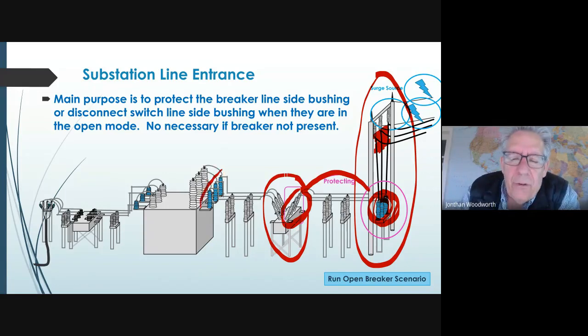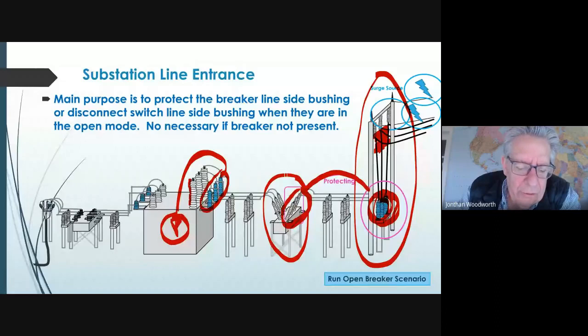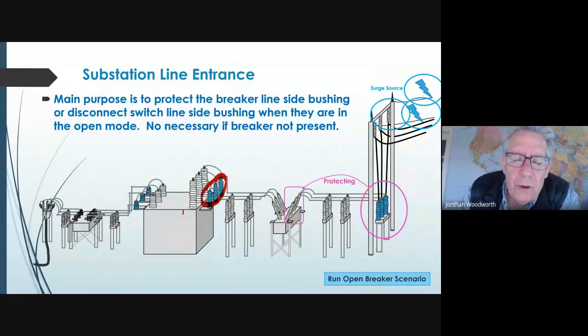The arrestors that you see on the transformer are all about protecting the windings on the inside. Yes, they do protect the bushings here, but the real purpose is the windings. So in this case, these arrestors here are protecting the primary windings, and these arrestors are protecting the secondary windings.